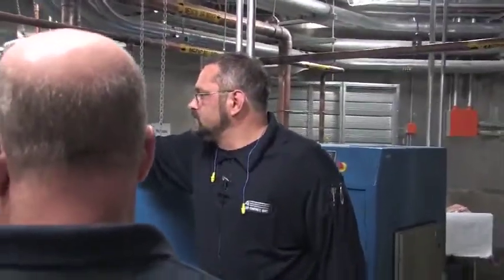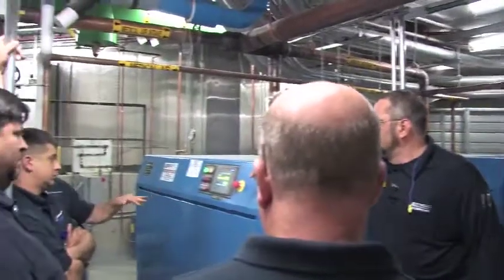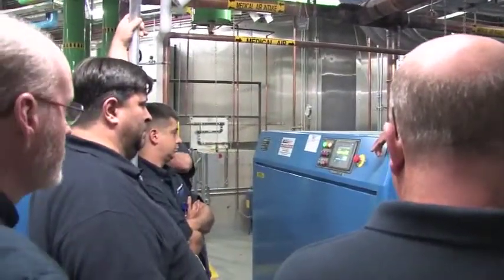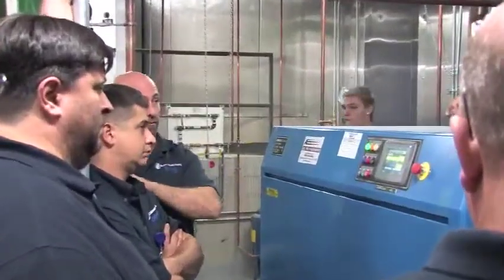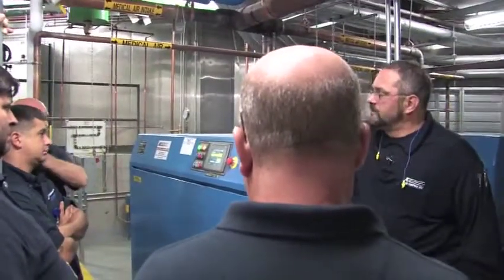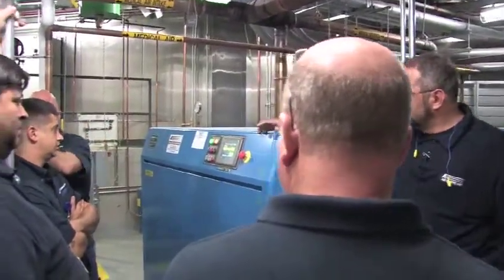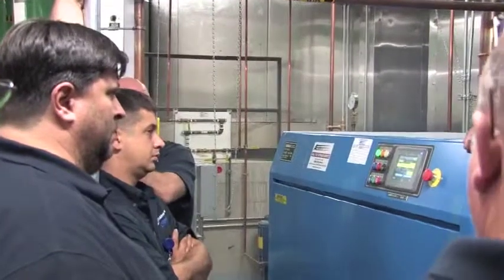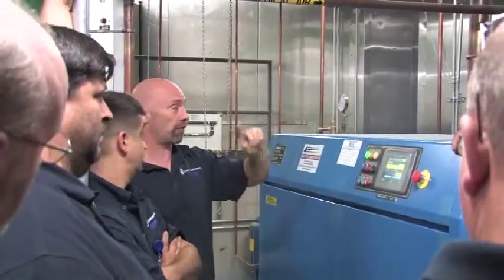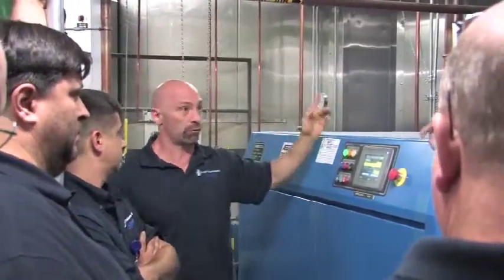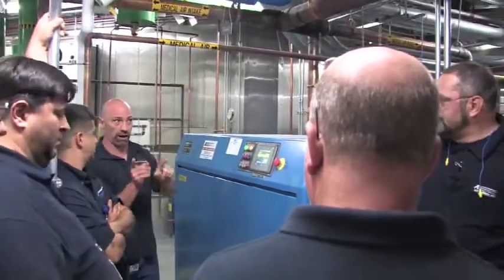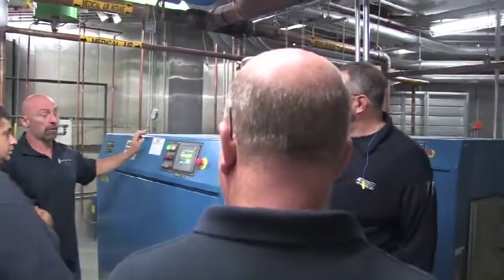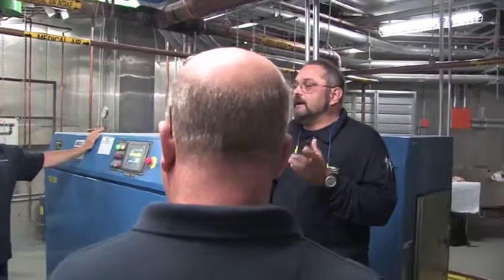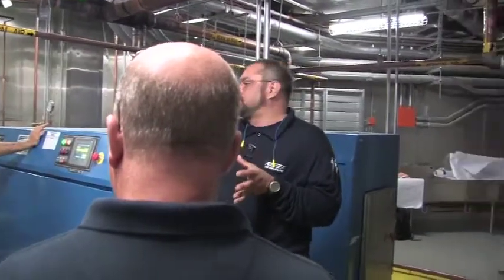So for normal operation, it's all sequenced. This is always going to be the lead compressor. No, it won't be the lead, it's the master. Right, okay. The master never changes, but the lead will rotate. What I'm trying to say is this one is the one that's going to get the most use. It's never going to switch. That master will never alternate, and these are kind of like volleyball. Oh no, the use will stay even on all of them. Well, the only thing that's a master is, let's visualize it this way.